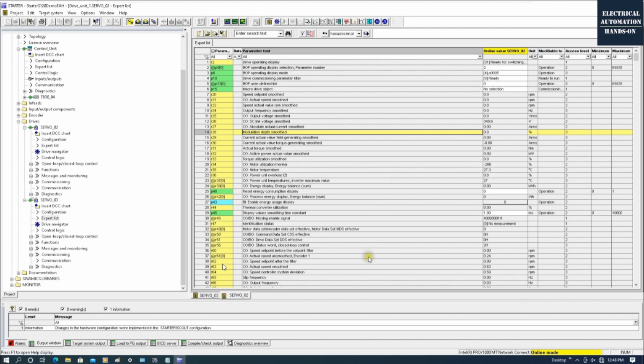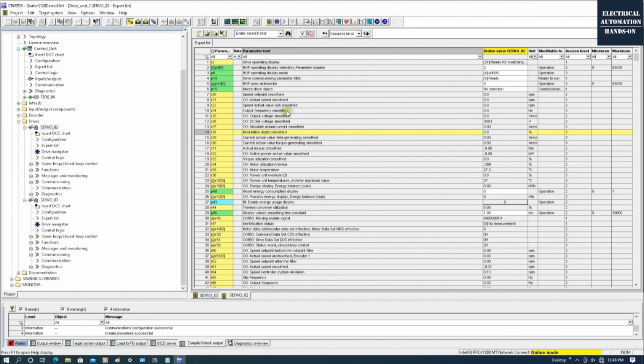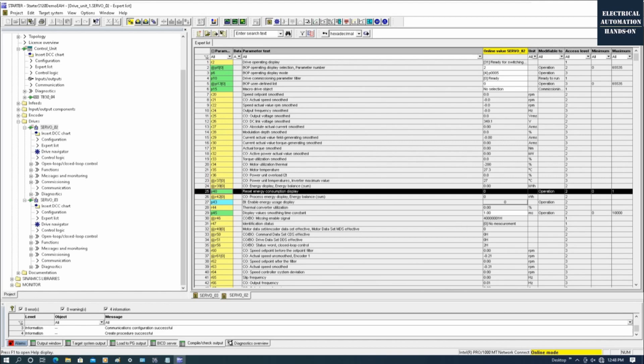We will set the same parameters for the Servo 3 for the blue motor. Basically, the P210 we will set to 345 for this demo. And then we set P1244 and 1248 for the DC bus, the upper and the lower threshold. Okay? So this is the Servo 2 and the Servo 3. And now keep in mind one thing. All the settings so far were online.